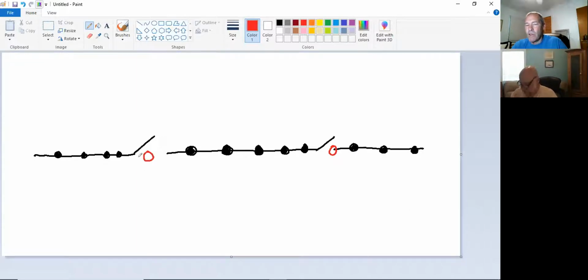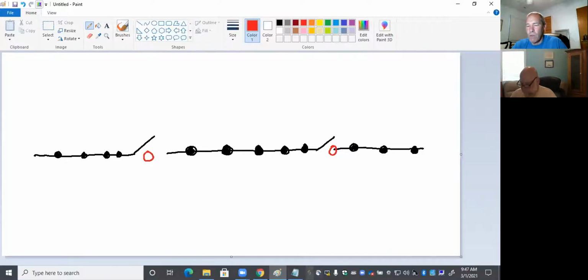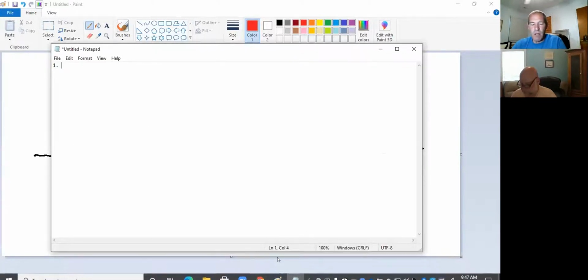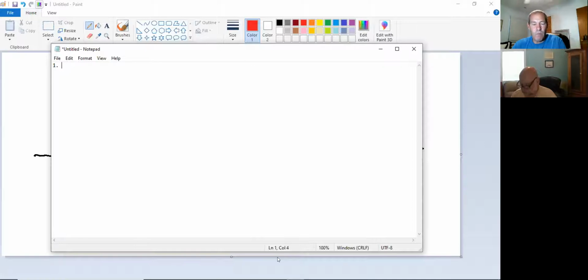So even though the breaker is open, and you can confirm in the middle that I don't have any voltage, and you can test with a tester that I don't have any voltage, you still cannot ground it or work on it until you see a visual. It's got to be a visual open point. Okay? So, first step in the process here, confirm two open points, which we've done in this drawing right here.